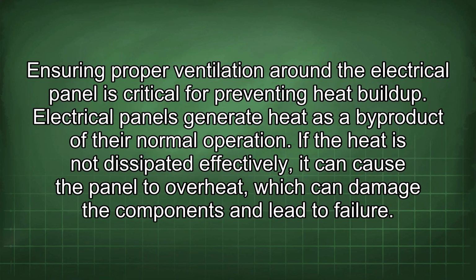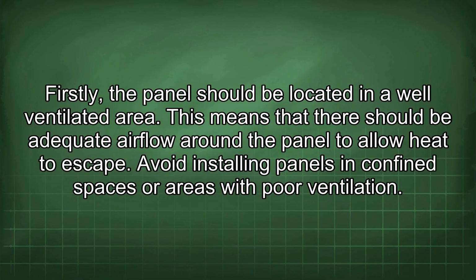Ensuring proper ventilation around the electrical panel is critical for preventing heat buildup. Electrical panels generate heat as a byproduct of their normal operation. If the heat is not dissipated effectively, it can cause the panel to overheat, which can damage the components and lead to failure. Firstly, the panel should be located in a well-ventilated area. This means that there should be adequate airflow around the panel to allow heat to escape. Avoid installing panels in confined spaces or areas with poor ventilation.